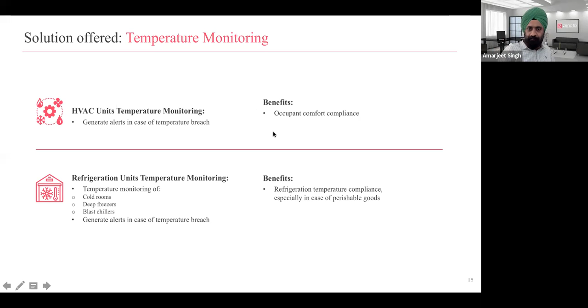We went beyond monitoring into control as well. So beyond energy and temperature monitoring, we did direct control of AHUs, exhaust, DFAs, FAs, pumps. We controlled several of them via VFDs - AHUs, exhaust, CT fans, and FA units. Direct control is the on-off control, and then we did control of some equipment via VFDs, and modulation of valves through our wireless IO cards.